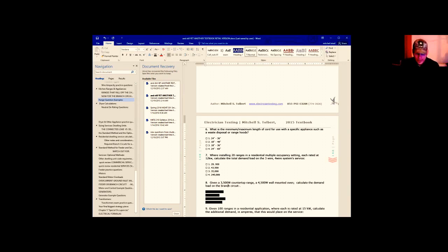So what I'm going to do then is take the 8,000 watts and treat that as if it's just one range rated for 8,000 watts. So that puts me on row 1. Now, I didn't change columns because I'm still at 8,000, which is within that range of column B. But instead of using 65% against 8,000, I'm using 80% against 8,000. So I take 8,000 times 80%, and that should give you 6,400. And that's my method to solve for a branch circuit.